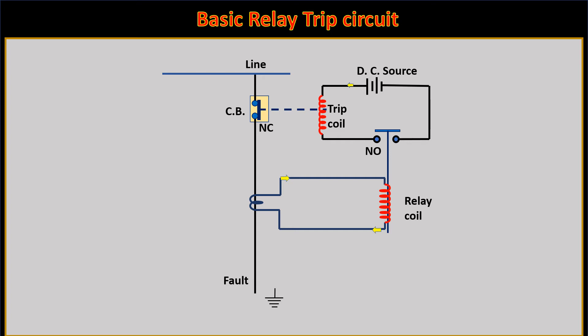Under abnormal conditions, current, voltage, phase angle, and frequency may change. The relay operates when it detects the fault, which completes the trip circuit and thus opens the circuit breaker, disconnecting the faulty circuit. A protective relay is a device that detects the fault and initiates the operation of the circuit breaker to isolate the defective element from the rest of the system.